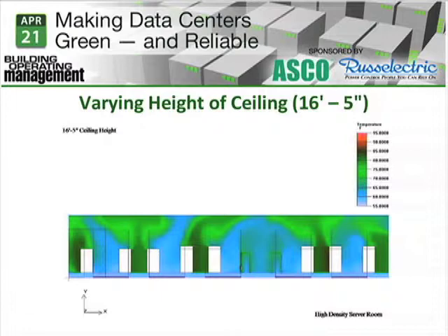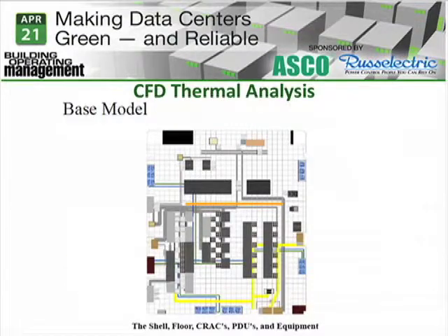You could see that by the fact, and they actually had a cavernous area that they could increase the ceiling height, which we did for about $110,000 after the study was done, and in fact, they needed no more equipment. But that's the power of some CFD models. Let's see the CFD thermal analysis here.